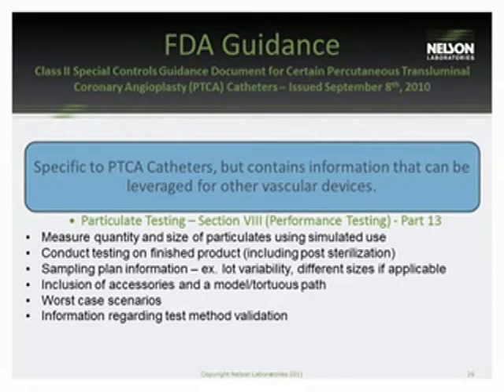We haven't found sterilization to typically increase particulate matter very much, but it's one thing that can be done to decrease arguments. As any of you who have been involved with submissions to the FDA know, it's always good to get rid of as many of those arguments as possible. Sampling plan information is important concerning lot variability and different sizes. We've seen some hang-ups considerably with stent systems, where there may be several different sizes, even material composition of the stent itself. It's always good to have several different sizes and types of your device if there is any type of variability in the size or composition of the device or product.